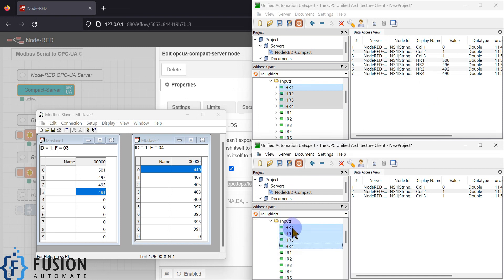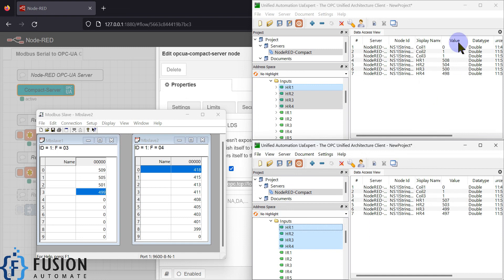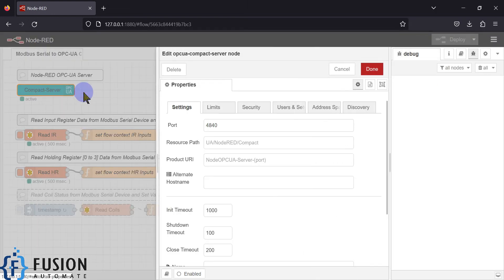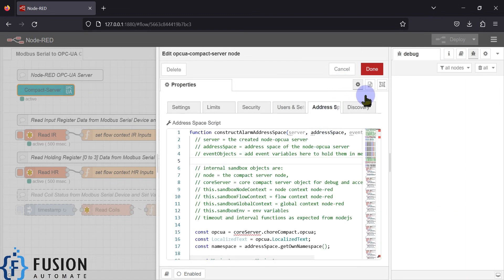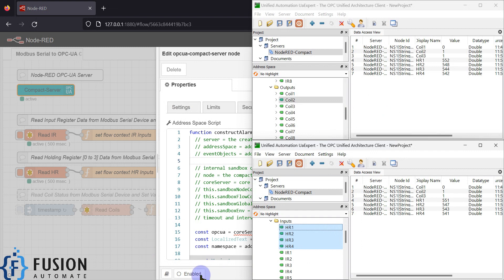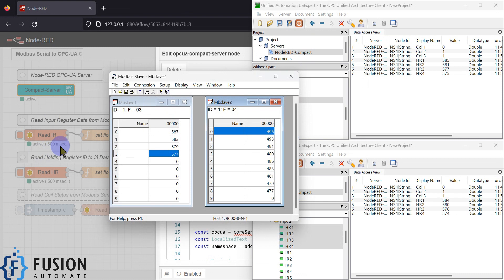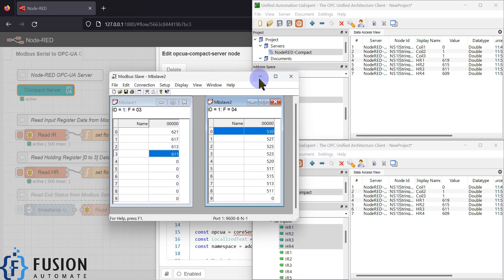Modbus serial to OPC UA conversion is happening, but you can also communicate between two OPC UA clients using the output address space. I'll show you how to create those output address space entries in the Compact OPC UA server. So I hope it's clear how this demo works: if you have connected Node-RED with any Modbus serial device, you can read the data in Node-RED, publish it to the OPC UA server, connect multiple clients to read those data, and multiple clients can also communicate with each other.